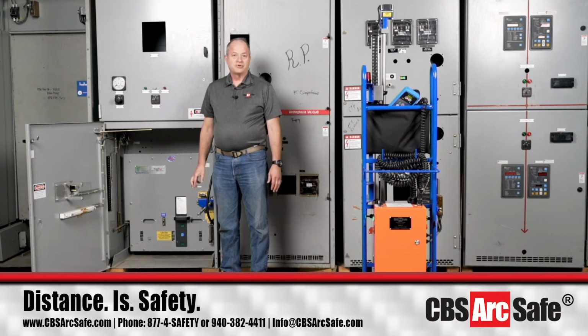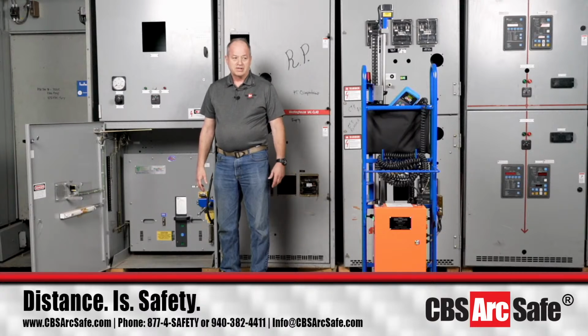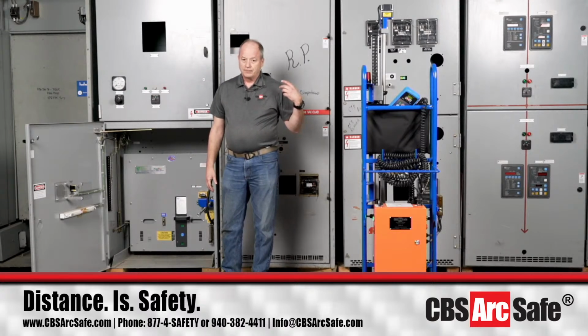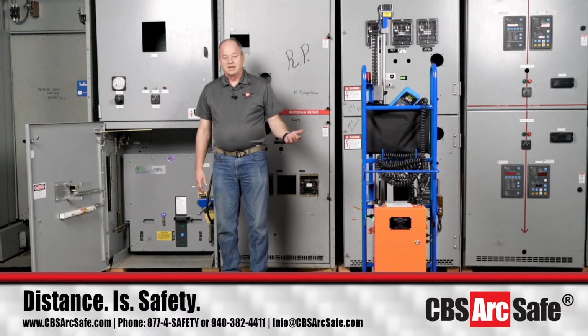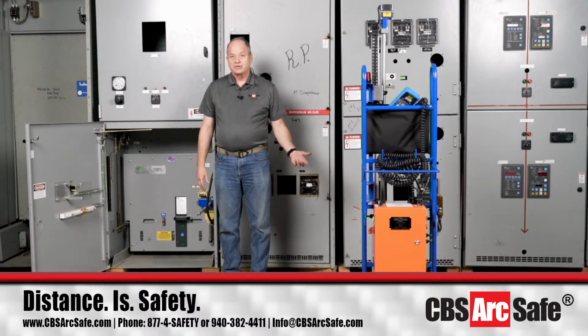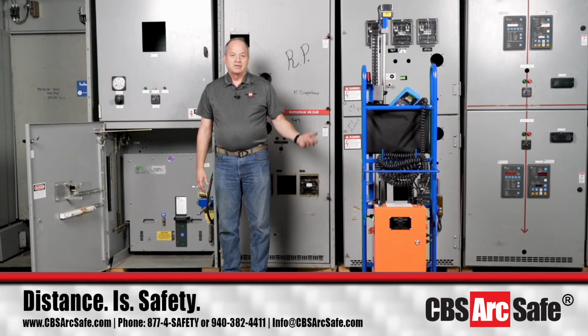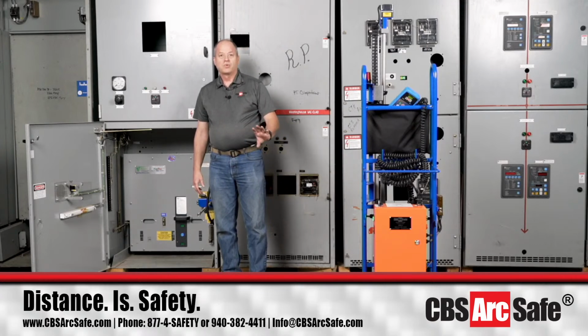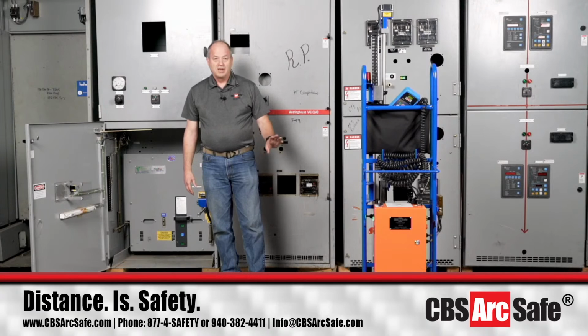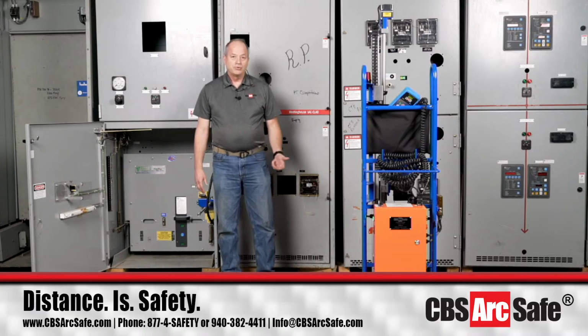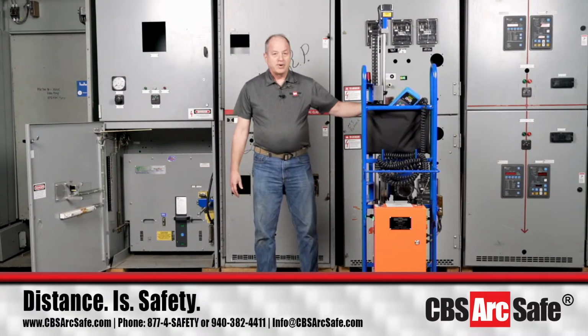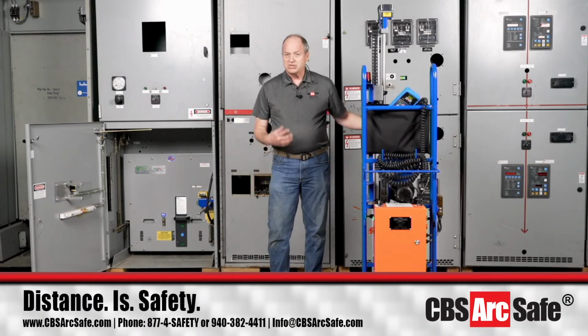I had that happen the first year I was working for CBS ArcSafe at a power plant up in Missouri. We'd racked the circuit breaker in and out plenty of times, and at the end of the day they forgot to put the fuse blocks in. So they put the suit on to do it, and they thought that the circuit breaker was broken. We hooked it up to a tester. They racked it in all the way, and when I noticed that the word connect was past the window, I simply used the manual tool to back it up to the window, and the breaker functioned properly. It wasn't broken, it just had wear and tear in it.